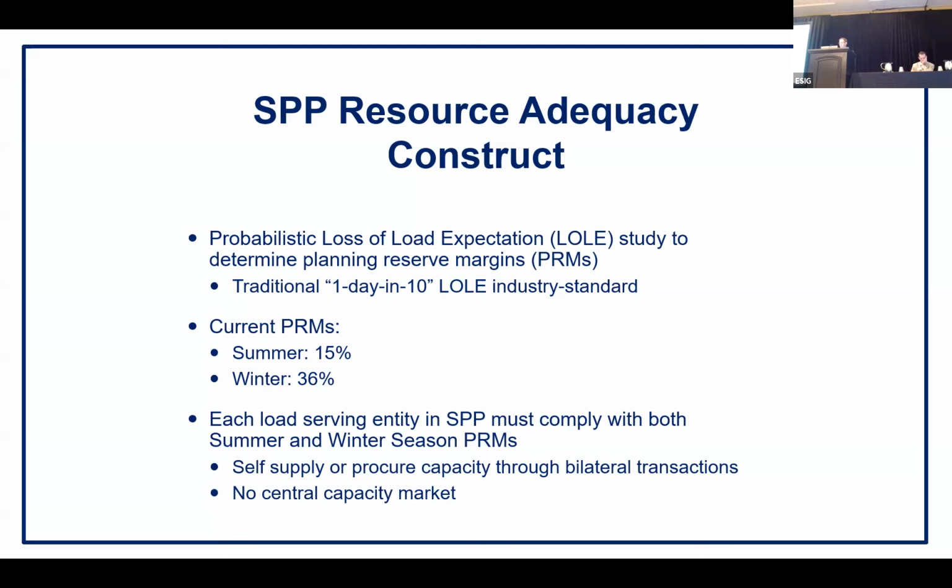The other interesting thing with SPP, we are all completely vertically integrated utilities. We're not restructured, as in this part of the country, you're more versed in that. So when we set up a summer or a winter PRM, it is simply up to our load serving entities to either build that capacity or go out and find a developer who's got it, or to buy it through a bilateral transaction. There is no central capacity market. So I get to read the headlines about all the other regions that deal with a capacity market, but we do not have a capacity market.